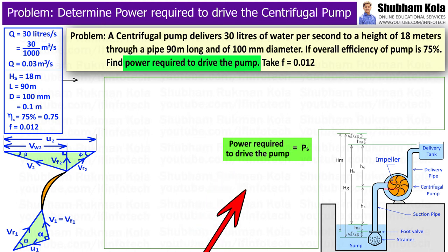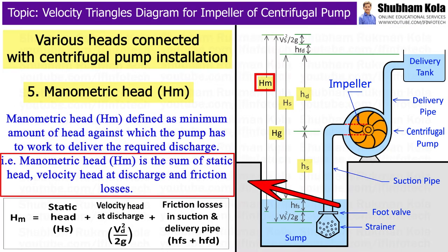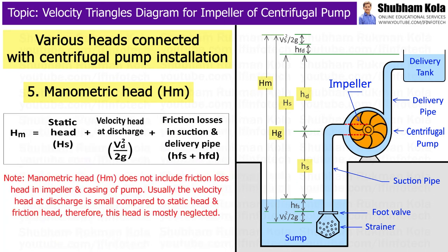So, to calculate this value, we use the equation of overall efficiency, where Hm is manometric head. Manometric head is the sum of static head, velocity head at discharge, and friction losses. But it should be noted that manometric head does not include friction loss head in impeller and casing of pump.